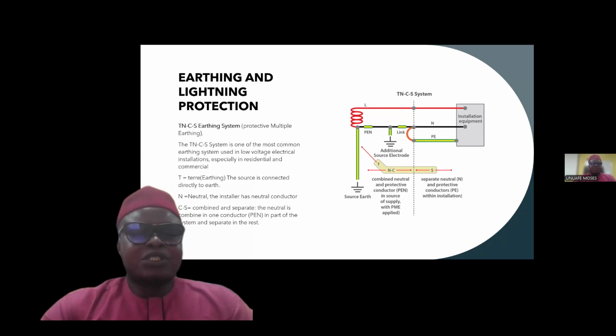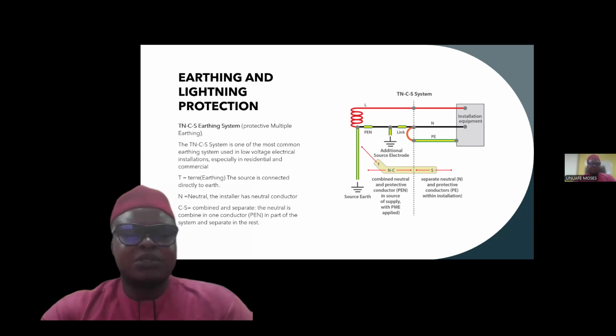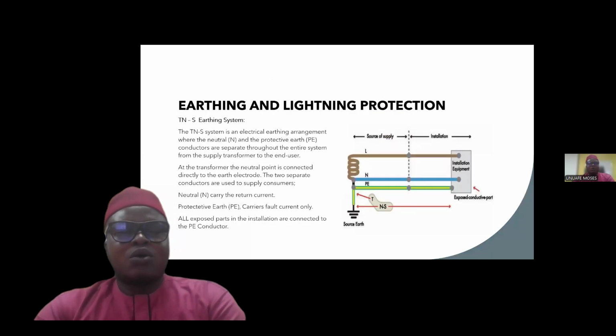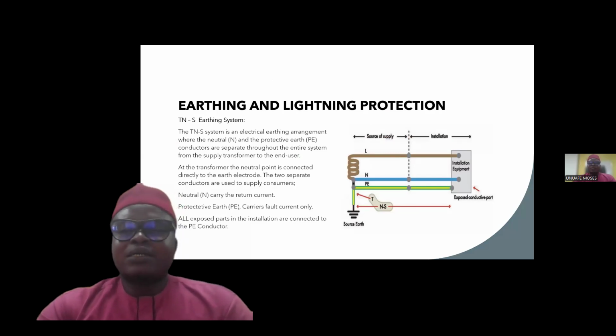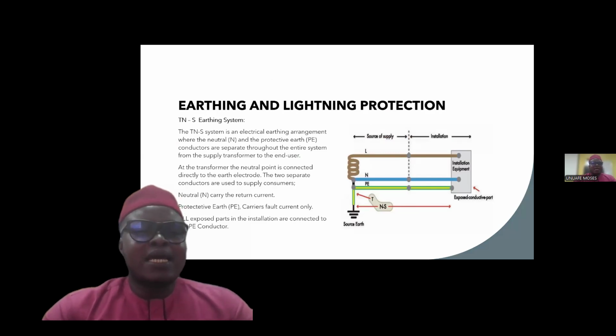So this TN-C-S system, the T is the source of connection direct to the earth, while the neutral is installed as a neutral conductor, while the C combines the separate neutral and earth into one conductor, which is PEN, in part of the system, separating to the rest. Now, if you look at the drawing, you will see that we have a PEN, which is protective earthing and neutral. So definitely on this very connection, you have the neutral connected to the earthing system, which is a PEN system. Now, there is a need to also know another type of the earthing system, which is the TN-S earthing system.